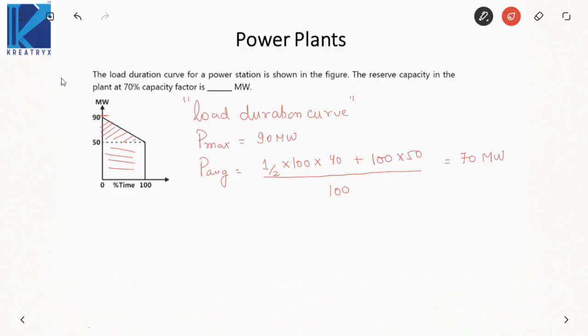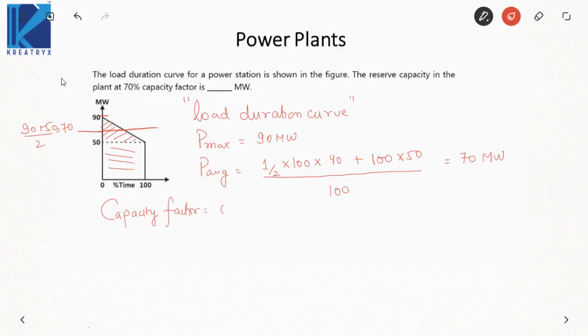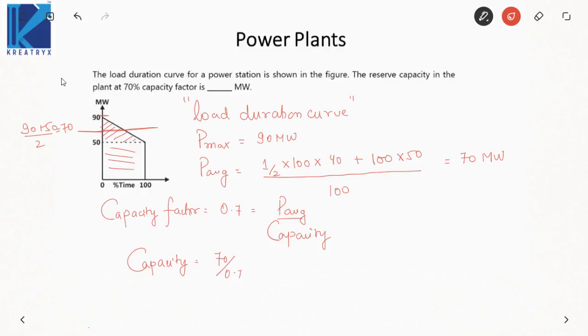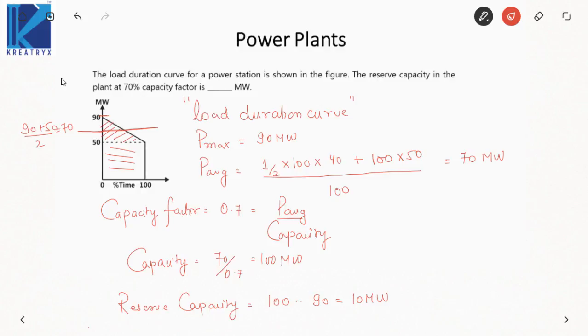Whenever you see a straight-line variation, the average is maximum plus minimum divided by 2, giving 70. But remember, this is only valid if the curve is a straight line. Now, capacity factor is 0.7, and it equals average demand divided by capacity. So capacity equals 70 divided by 0.7, which is 100 megawatts. Then reserve capacity equals capacity minus maximum demand, which is 100 minus 90, giving 10 megawatts. That is the reserve capacity of the plant.